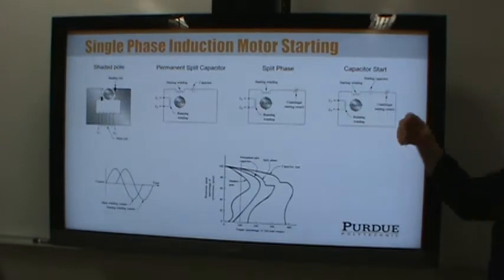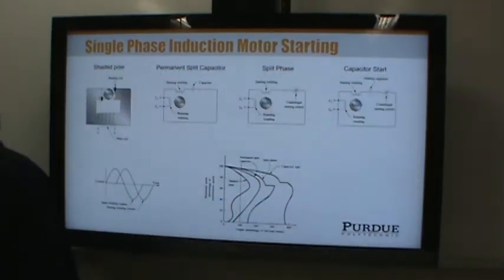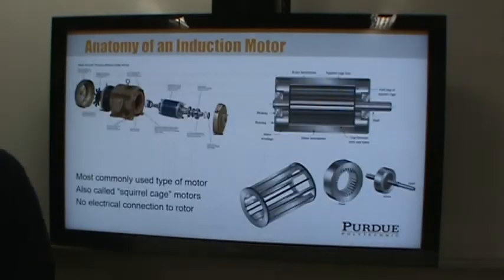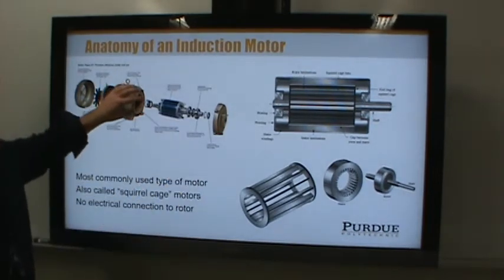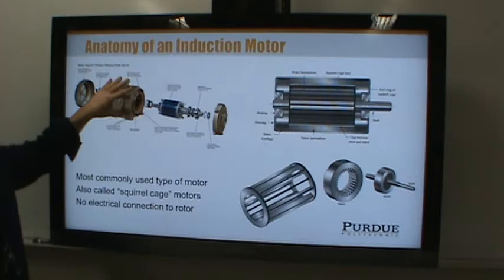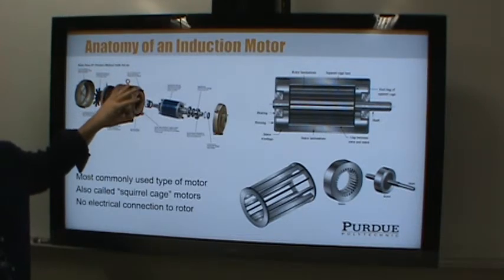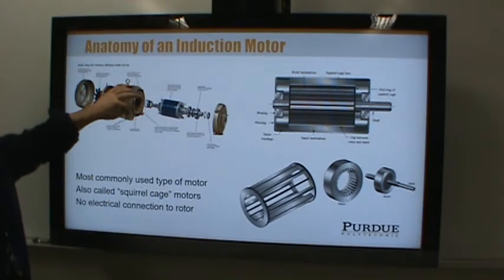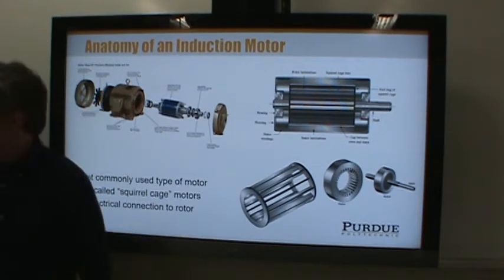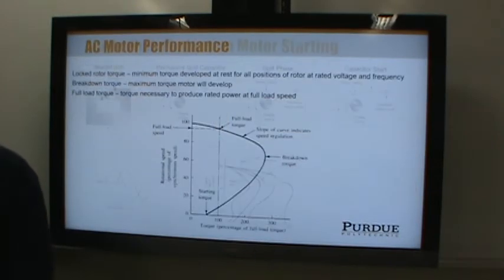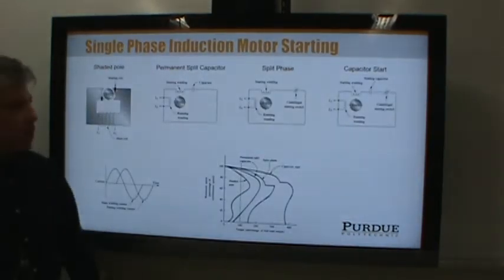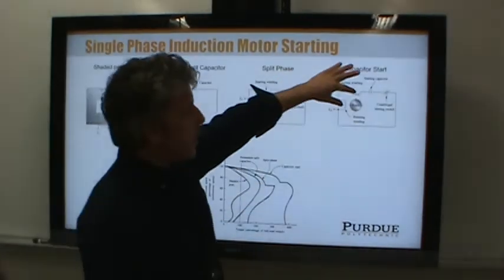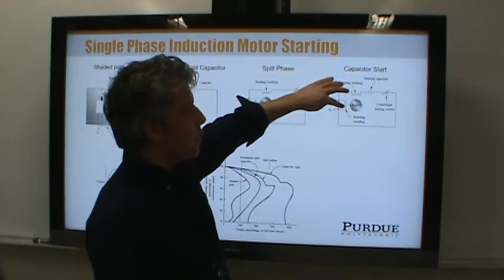These two windings are coils literally mounted in the stator. Your AC unit motor won't look like this large industrial motor, but it's the same principle. For the AC compressor you'd have two stator windings — one used for starting, the other not — probably in a hermetically sealed compressor.